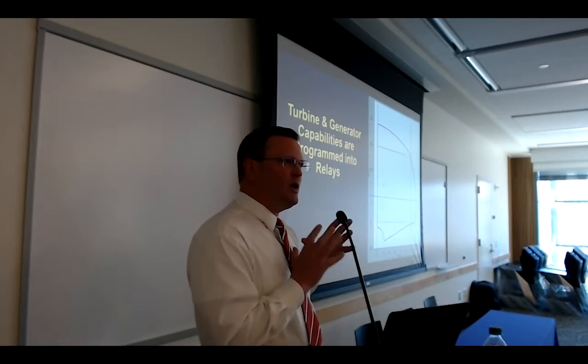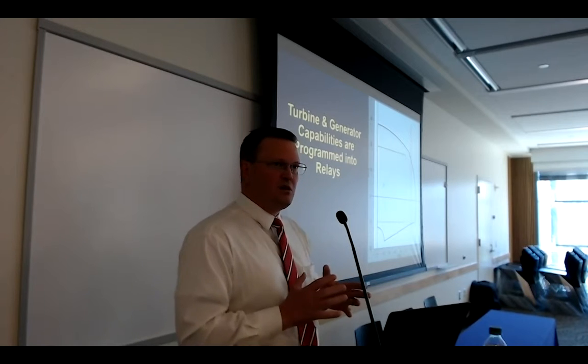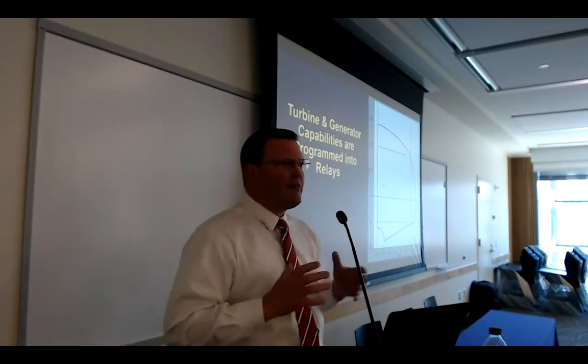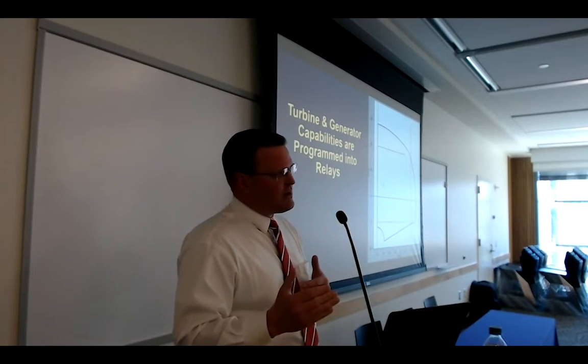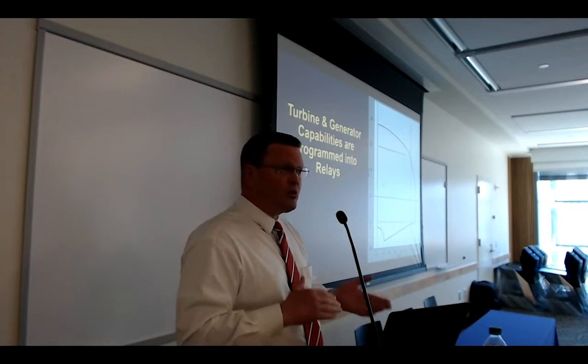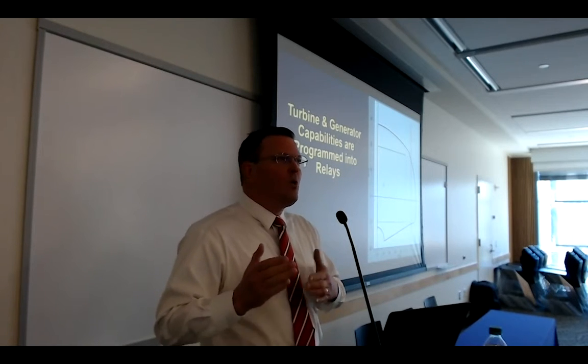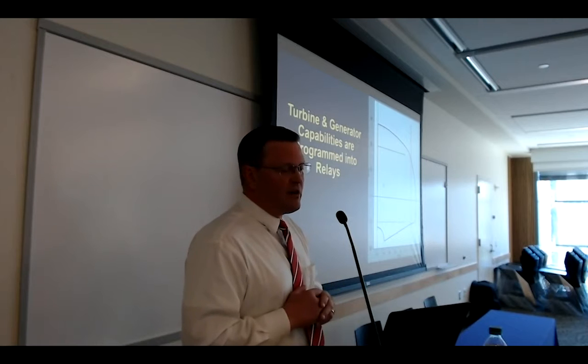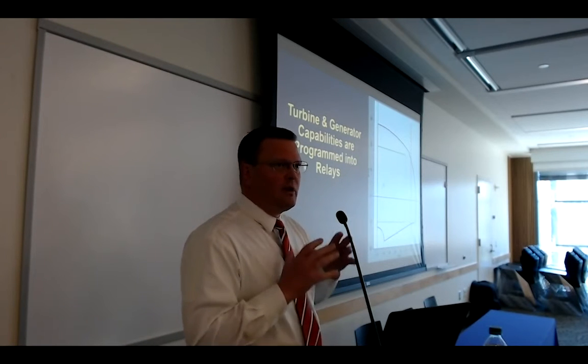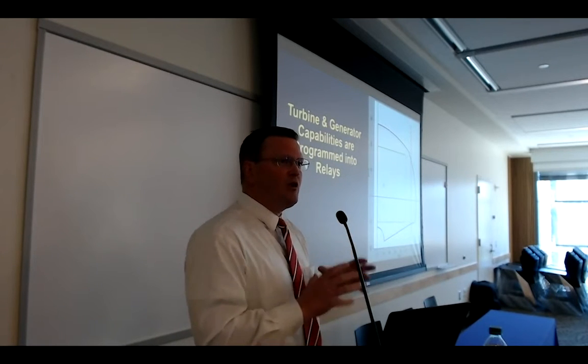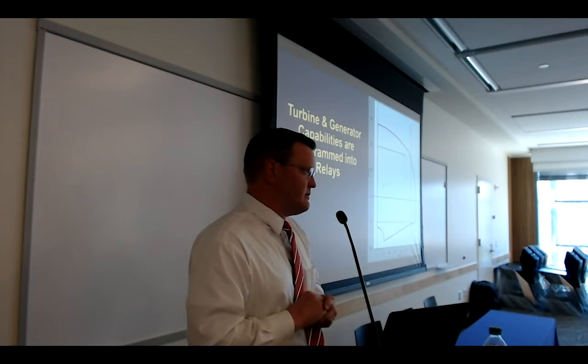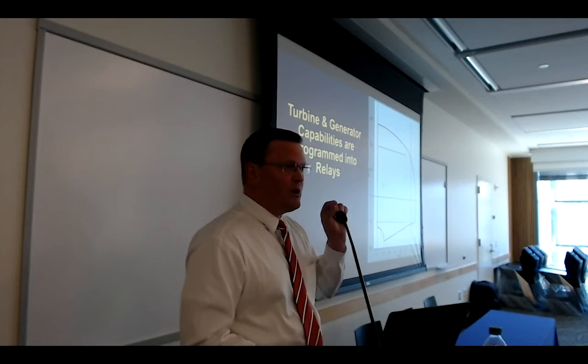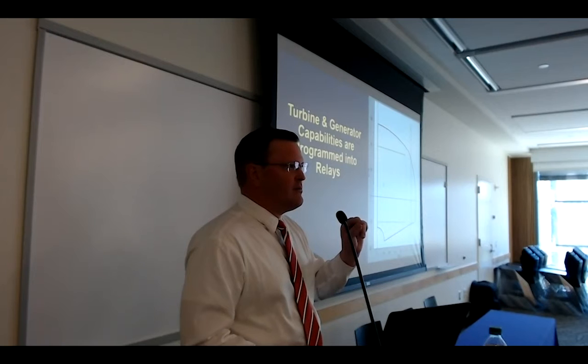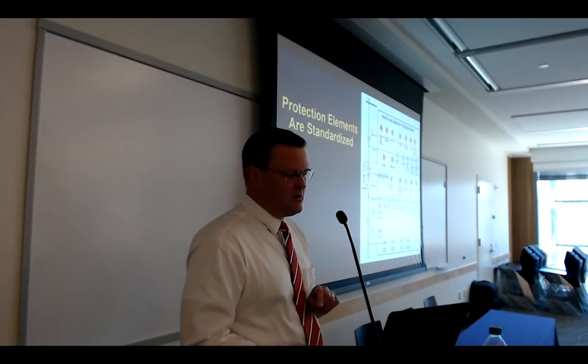Now these are critical to understand. As protection engineers and controls engineers, we have to know the reserve margins - the instantaneous, short-term, and long-term reserve margins. We also have to know when it's time to trip a generator off. These are programmed into relays in different ways. It's very important that we know where these lines are, because it's about saving lives.